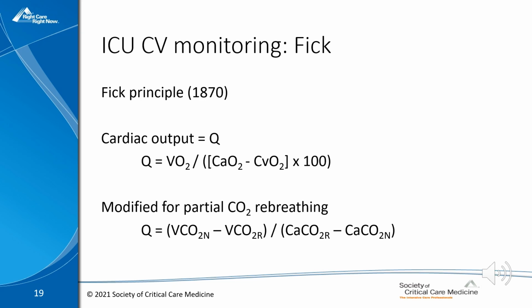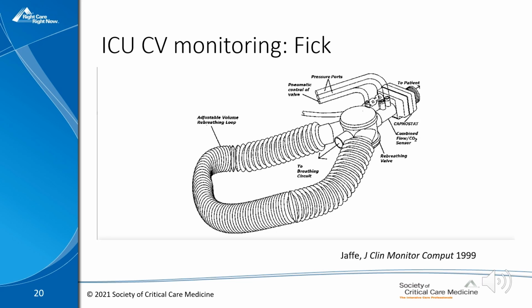This equation can be modified for partial carbon dioxide rebreathing, where the cardiac output is equal to the difference between the volume of carbon dioxide exhaled per unit time under normal conditions and then under rebreathing conditions divided by the arterial content of carbon dioxide under normal conditions subtracted from the arterial content of carbon dioxide under rebreathing conditions. This is performed by use of a proprietary partial rebreathing circuit that you can see pictured here.